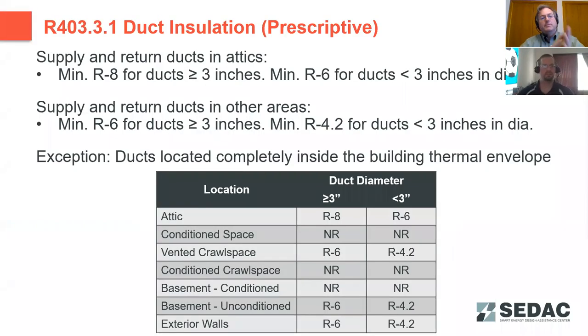Okay, and I will take over for the mechanical sections of the residential code. First thing we'll touch on is duct insulation requirements. Prescriptive requirements require supply and return ducts in attics to have a minimum of R8 insulation if the duct is greater or equal to 3 inches in diameter, and a minimum of R6 for ducts that are smaller than 3 inches. If they're in other unconditioned areas other than the attic, such as a crawl space or an unconditioned basement, then those drop slightly to R6 for the larger ducts and 4.2 for the smaller ducts. And we've put a summary table here for reference in the future with various locations and the insulation requirements.